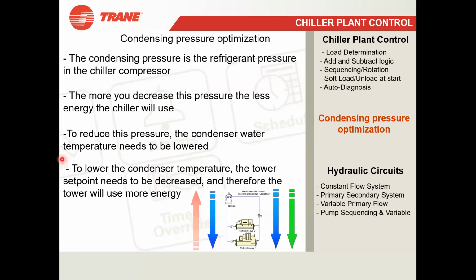So this is called condensing pressure optimization. But you must be thinking that now my cooling tower set point is decreased, that means my cooling tower will be using maximum energy now. But it is not exactly like that, because this CPC's target is to find the optimal tower set point. Tower means cooling tower, the optimal cooling tower set point, so that the energy used by the chillers and the towers is the lowest possible.